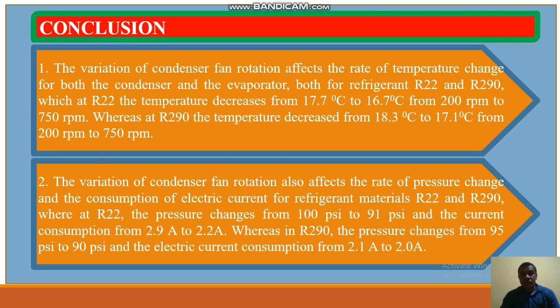The next conclusion is that the variation of the condenser fan rotation also affects the rate of pressure change and the consumption of electric current for refrigerant R22 and R290. For R22 the pressure changed from 100 psi to 91 psi, and the current consumption from 2.9 to 2.2 ampere, whereas for hydrocarbon or R290 the pressure changed from 95 psi to 90 psi, and the electric current consumption from 2.1 ampere to 2.0 ampere.